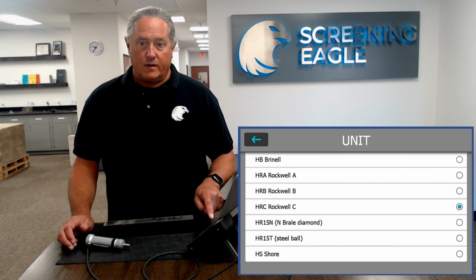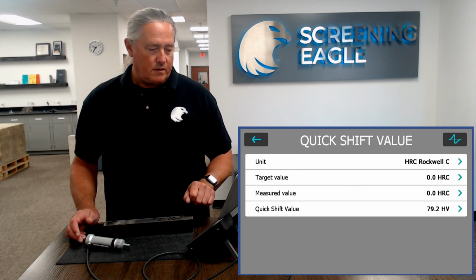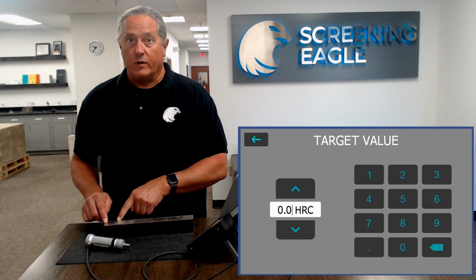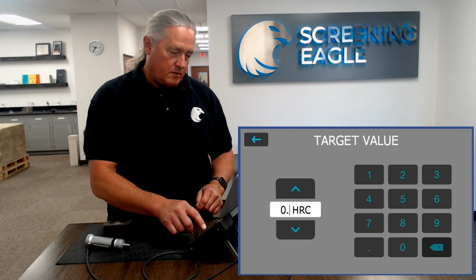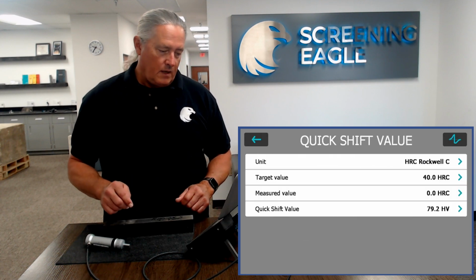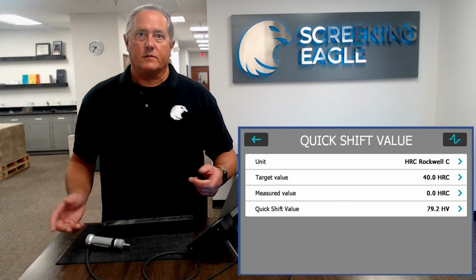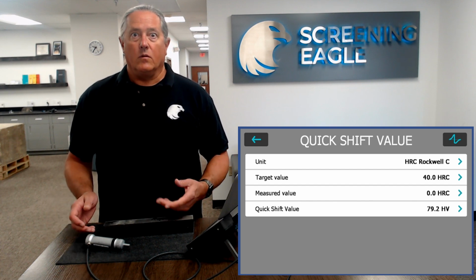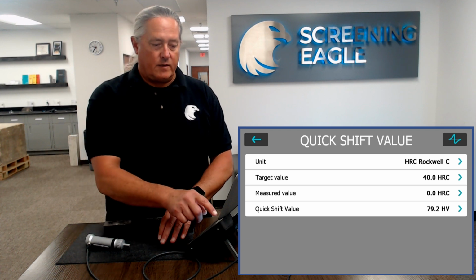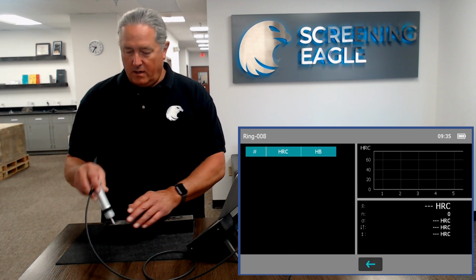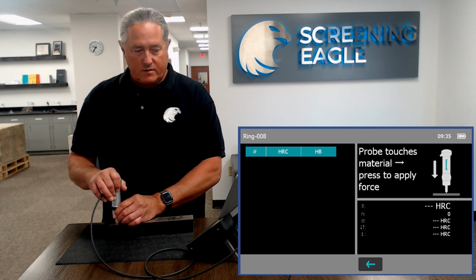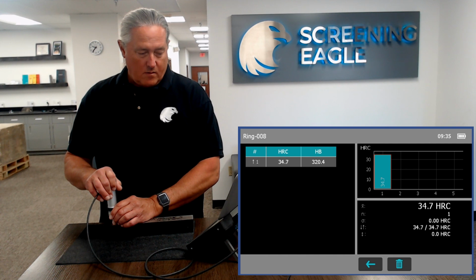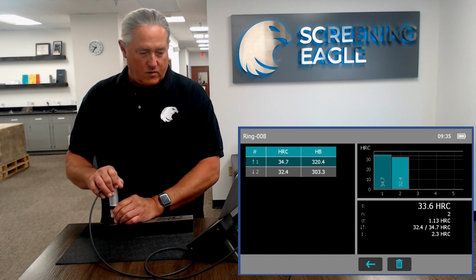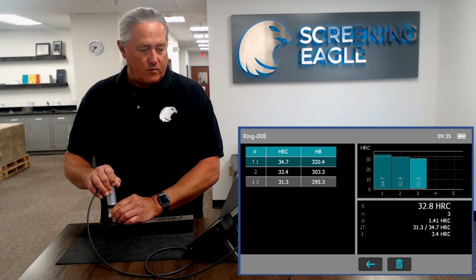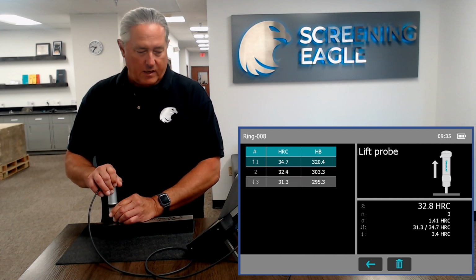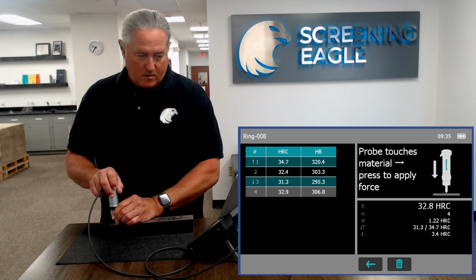Right? We choose our unit. So what units are we working in? Here we have Rockwell C, so we're going to leave it Rockwell C. The target value is that 40 Rockwell C that was calibrated by the laboratory. So we're going to enter that in. And now I can either enter in my measured value, which was that 31.8 average directly, or if I haven't already measured this piece, I can tap on the signal icon in the upper right hand corner, and I can take my 5 comparison measurements, and we're all going to be close to where that laboratory had tested to make sure we get a good comparative result.